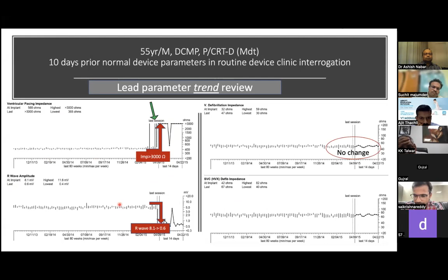So what is happening here? This green arrow shows the last session, which was normal. And then suddenly the pace sense coil impedance shot up from baseline to more than 3000. And at the same time, the R wave, which was 8.1, dropped abruptly to 0.6. This abrupt change is very important. And if you look at the defibrillator impedance and SVC coil impedance, they were normal.